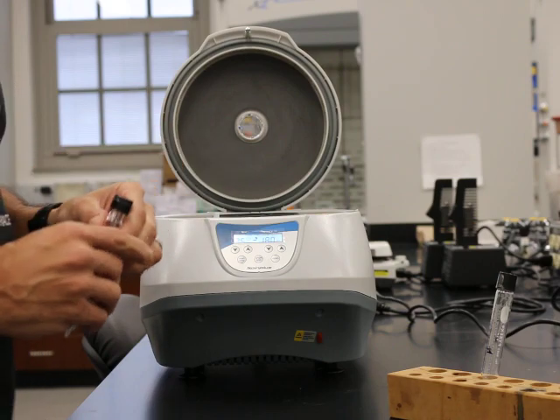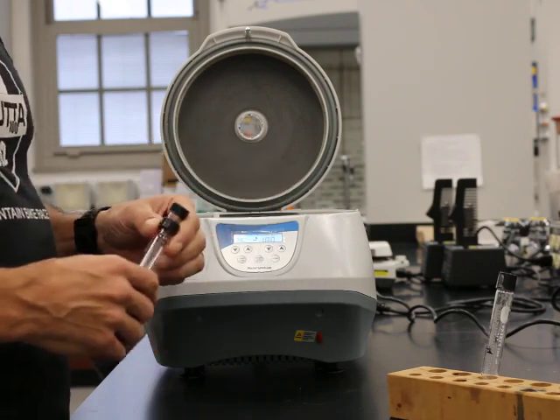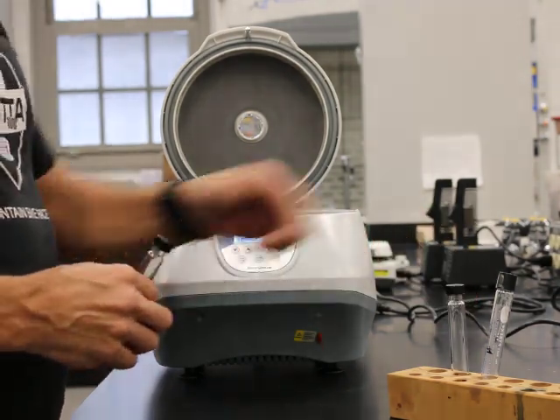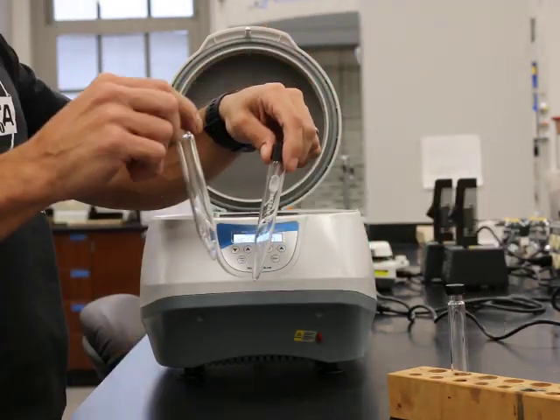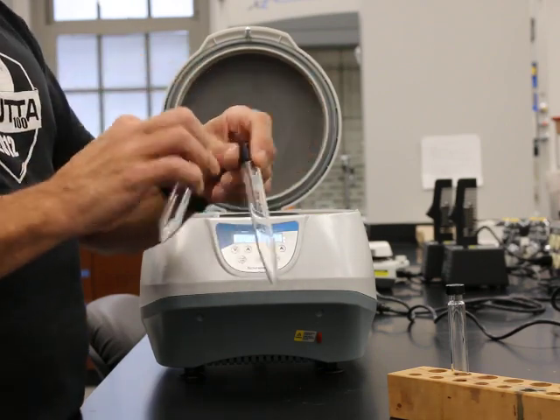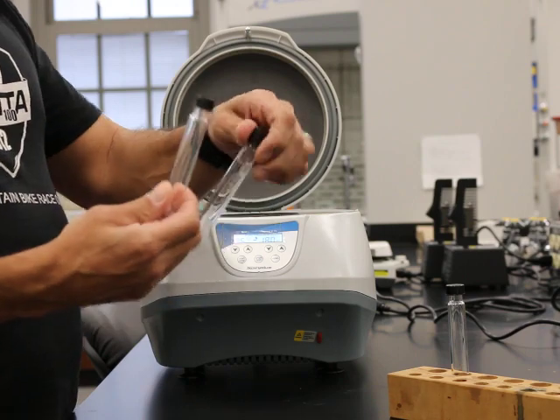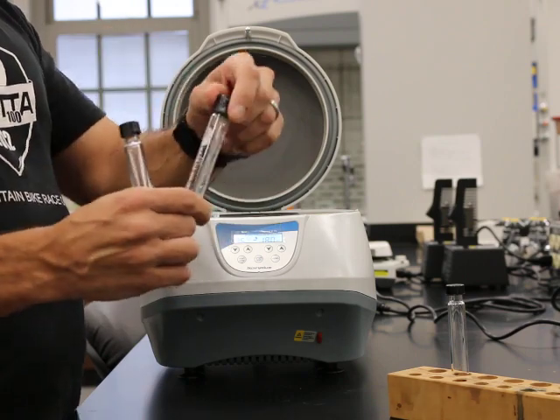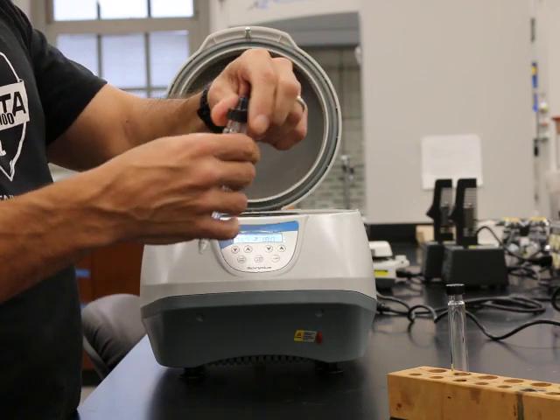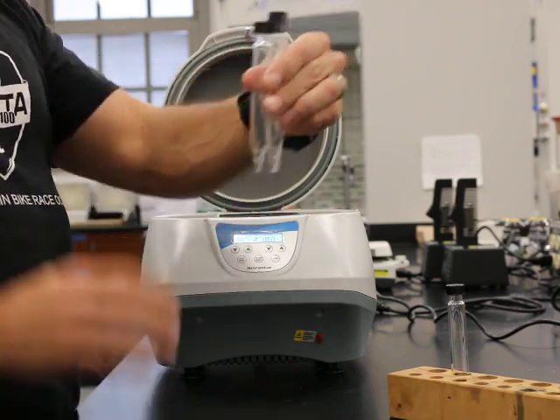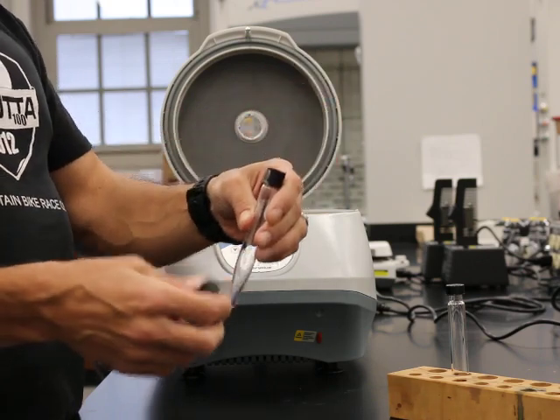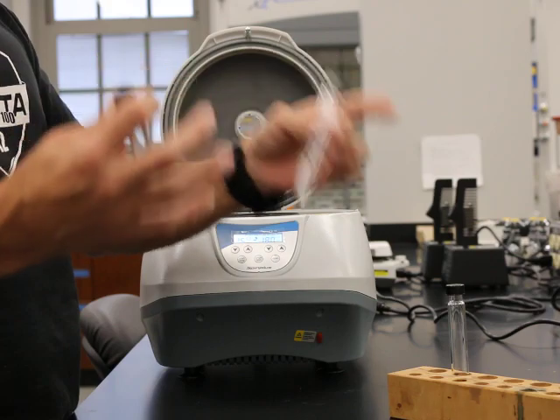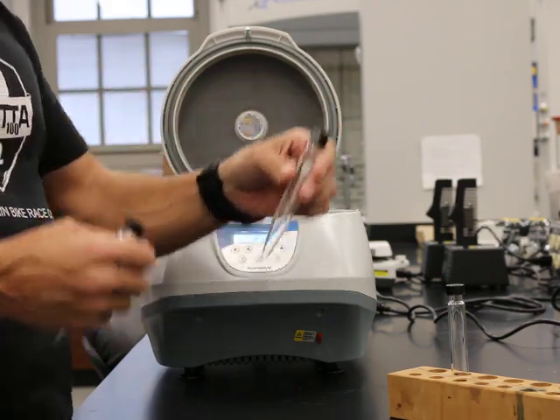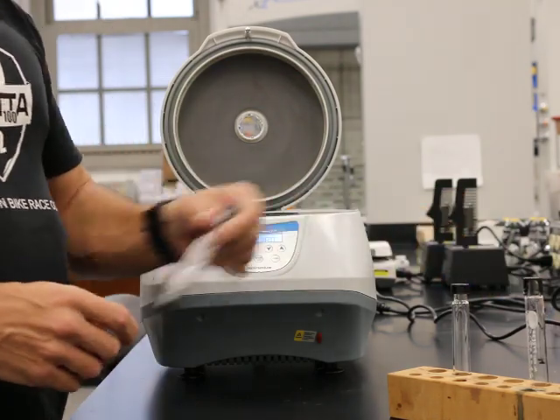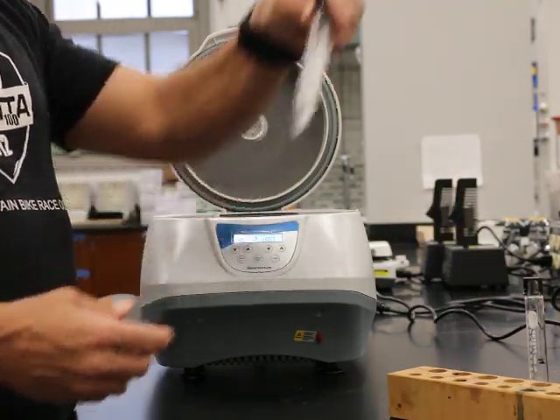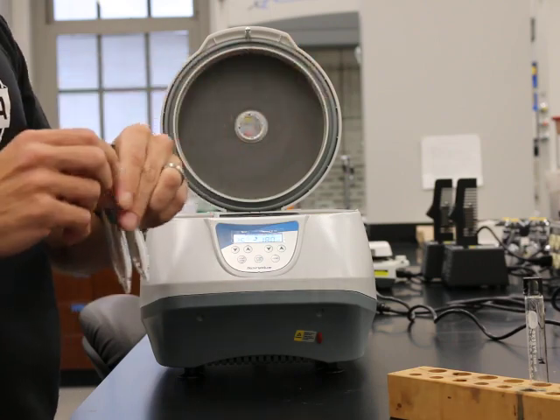The one thing that you do have to be cautious about in terms of balancing the load, unfortunately, we have two different types of centrifuge tubes floating around. We have some newer ones that don't have any labeling on them. There's no graduations. They have a thinner, smaller cap. We have some older ones though that are larger. They're visibly larger, which means they're heavier. And so if you try to balance one of these with the other type, it's not going to balance no matter how hard you try. So you need to pay attention to the pairs of centrifuge tubes that you're using. Make sure that they're the same and that they have the same amount of liquid in them.